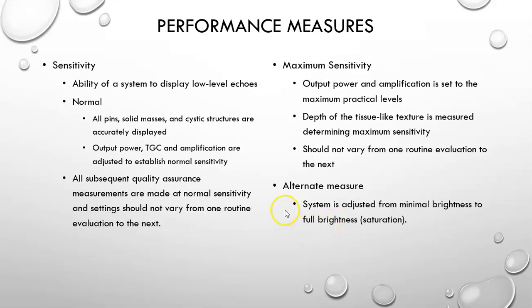The alternate measure is what you should be doing, and this is where the system is adjusted from very minimal brightness to full brightness, and you check where those settings occur. And the maximum sensitivity, if you turn down the gain until you start losing pixels in the lower portion of your image so that you're unable to see the actual structures of the image. In that situation, you've turned down your gain, and that is where you want to measure it from time to time, periodically, and that should be able to vary then from one evaluation to another if there's a decrease, diminution of output, sensitivity.